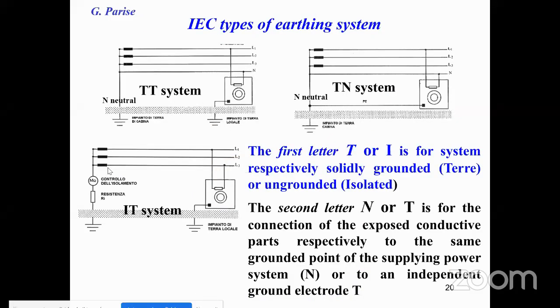For this reason, the condition of the neutral point is important, and the IEC type of earthing system is a very important definition. So the IEC approach introduced the TT system, TN system, IT system. The first letter, T or I, is for a system respectively solidly grounded, terre, ground, earth, in French, in Italian it is terra, so T, or ungrounded, isolated, so I: grounded or ungrounded.